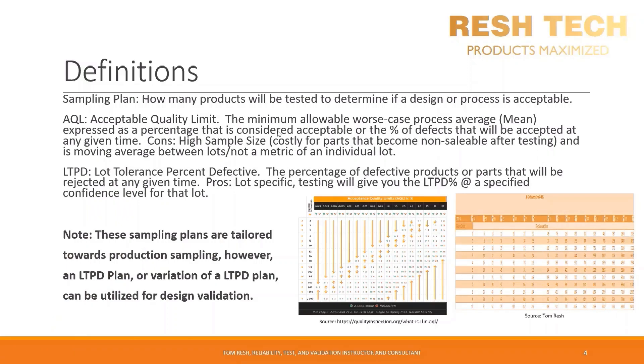Let's define a sampling plan. A sampling plan tells us how many products will be tested to determine if a design or process is acceptable. We're going to cover two types of sampling plans: AQL Sampling Plans and LTPD Sampling Plans. AQL stands for Acceptable Quality Limit, which is the minimum allowable worst-case process average expressed as a percentage considered acceptable — or the percentage of defects that will be accepted at any given time. A downside to AQL Sampling Plans is that they require a high sample size, so if you are performing any kind of destructive testing that degrades a product to the point where it cannot be sold to a customer, it can be very costly to your company.